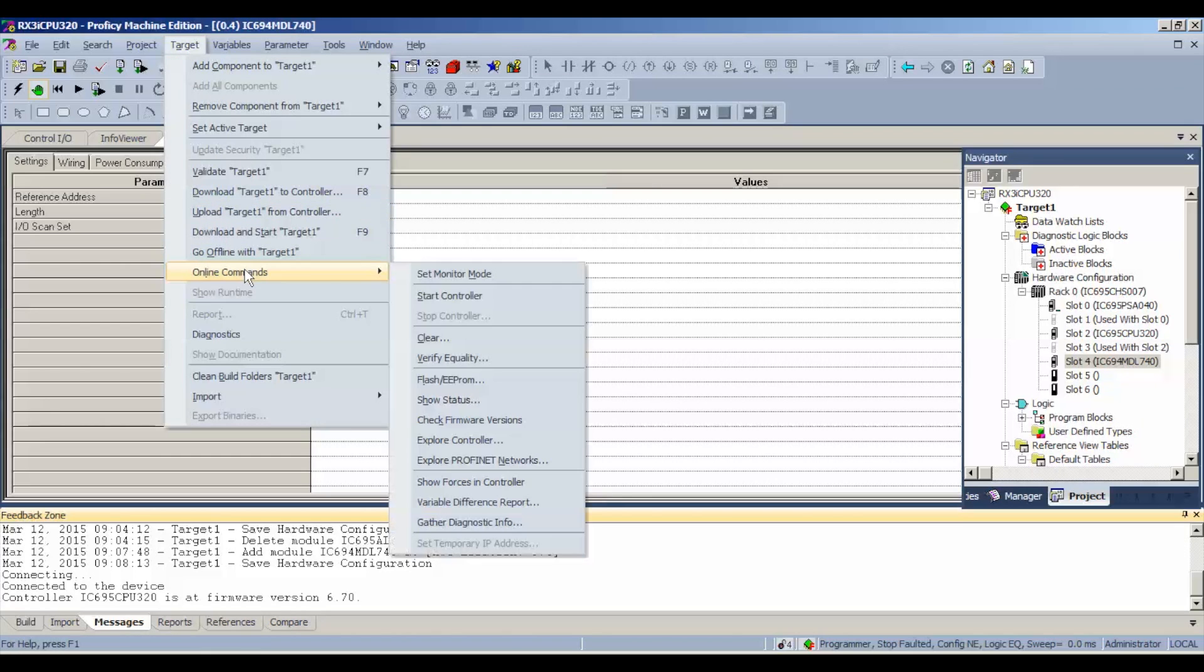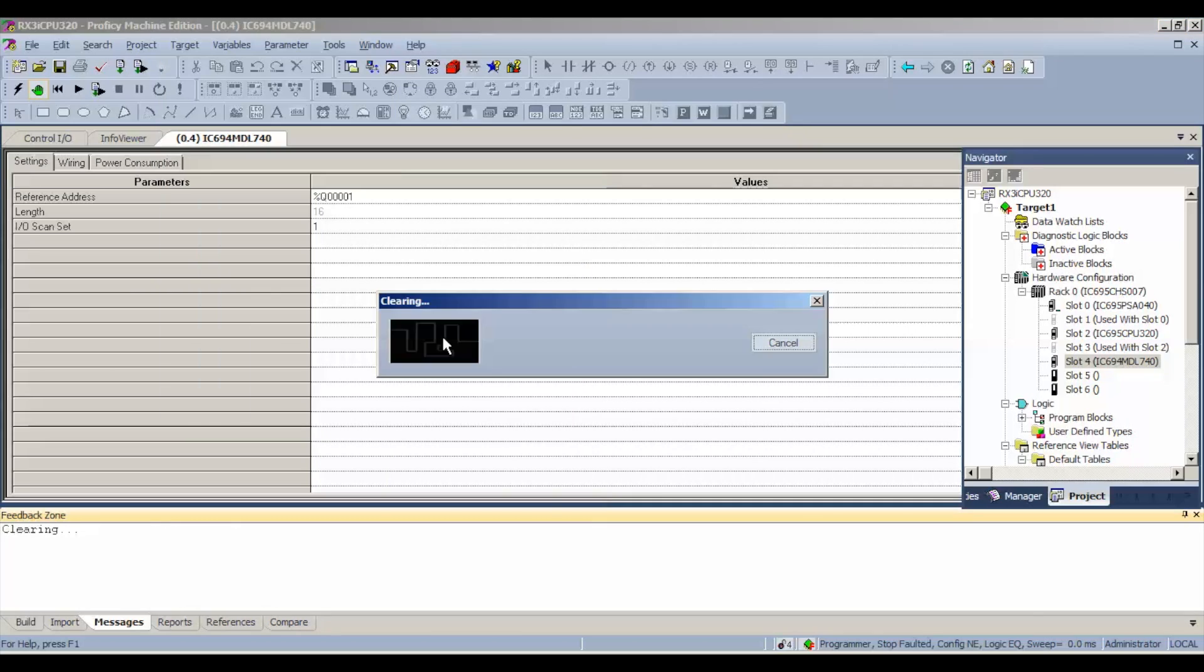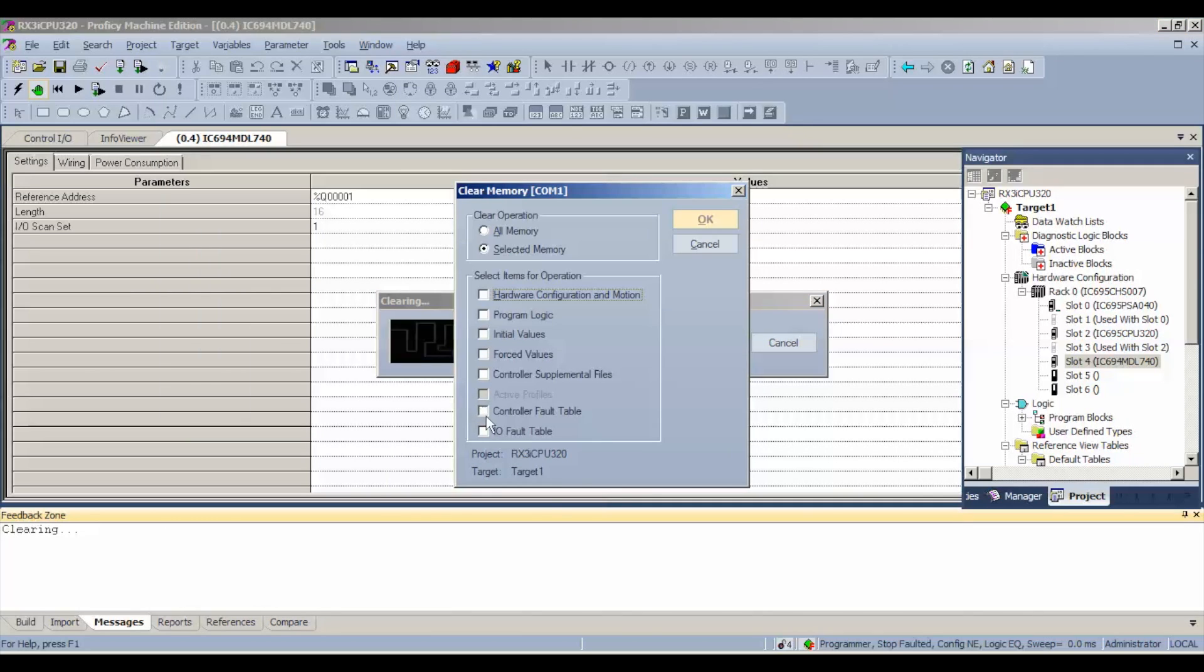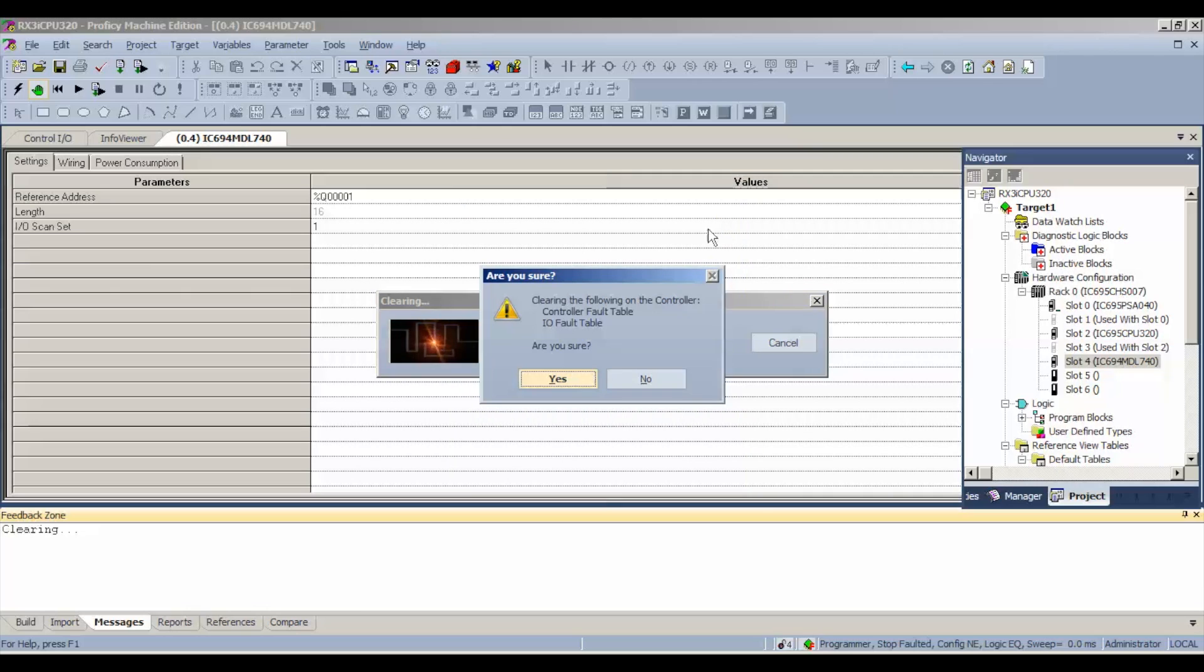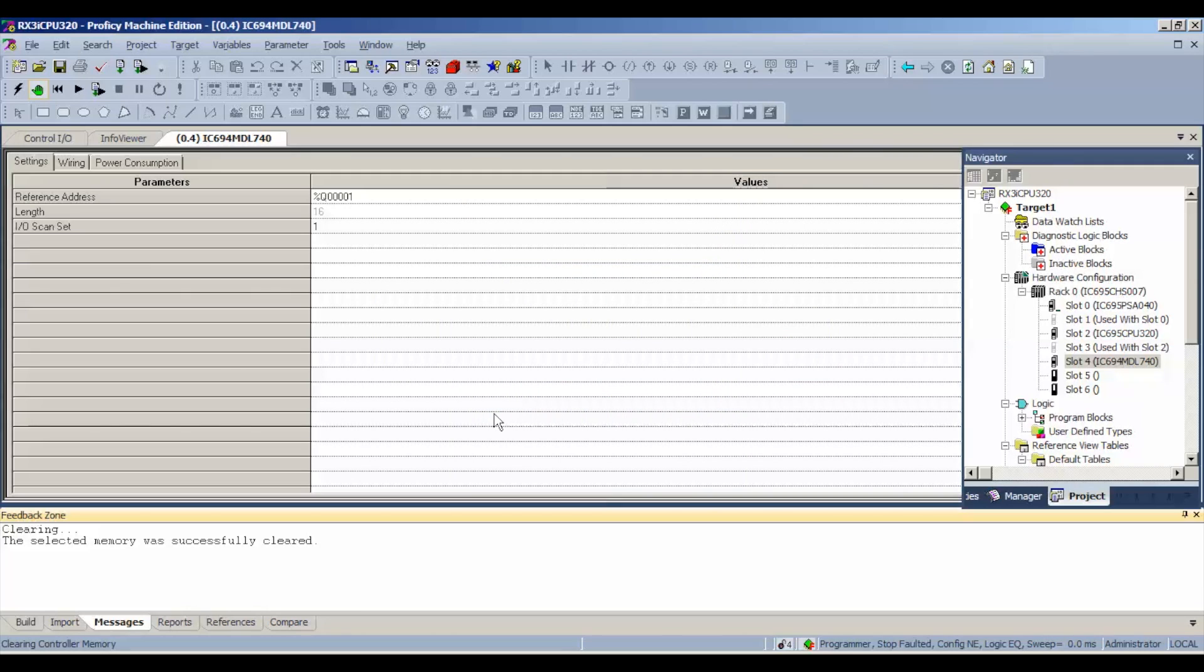So we're going to go to target, online commands, clear. We're going to clear that fault and the controller and I/O fault tables. Make sure you do that step, otherwise you're going to get hung up when we go to download and run.